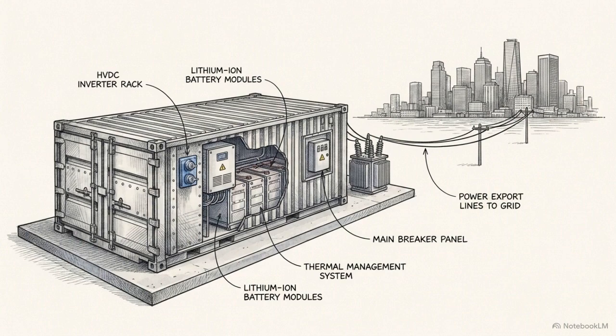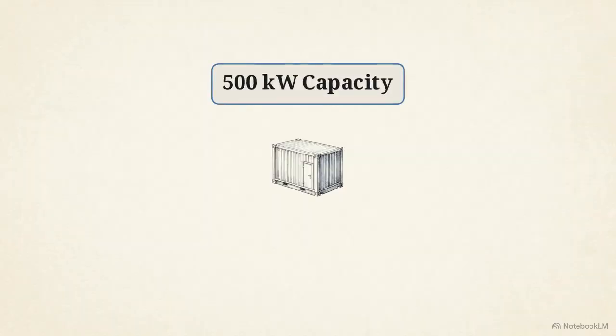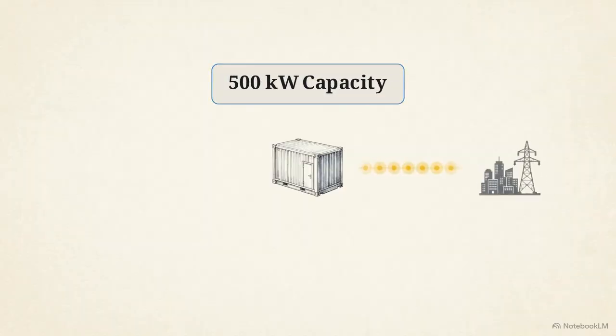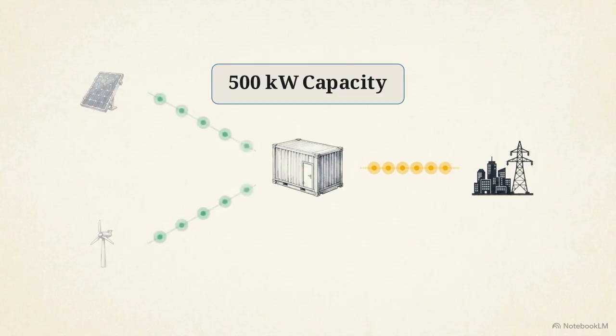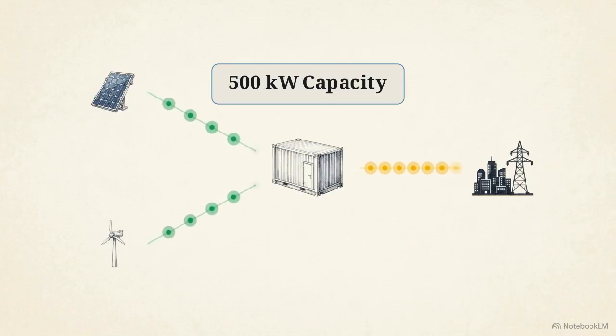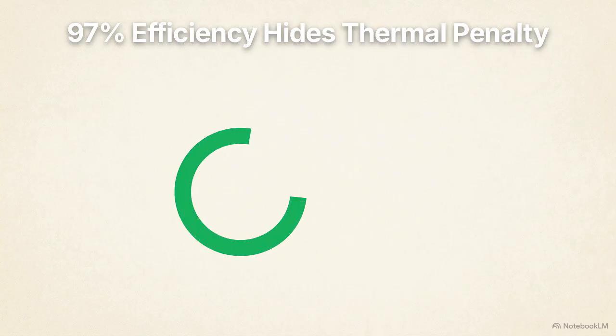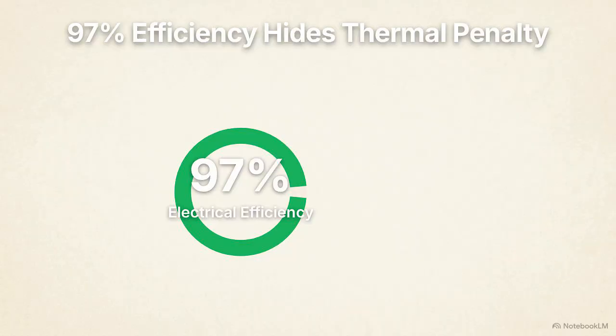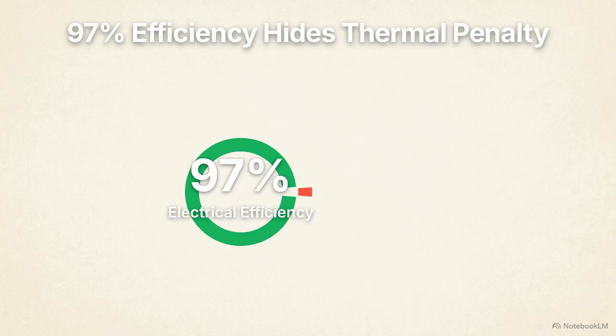An industrial battery energy storage system operating on the grid is a massive concentration of chemical energy. A standard storage container holds around 500 kilowatts of power, constantly discharging into the grid and recharging from solar arrays or wind farms. These systems are highly efficient, often operating at a 97% electrical efficiency rate. But the remaining 3% of that energy is lost, and in a closed thermodynamic system, that lost energy becomes heat.